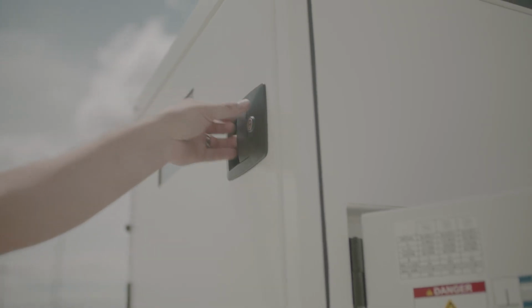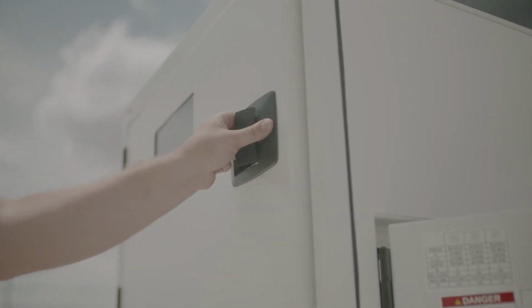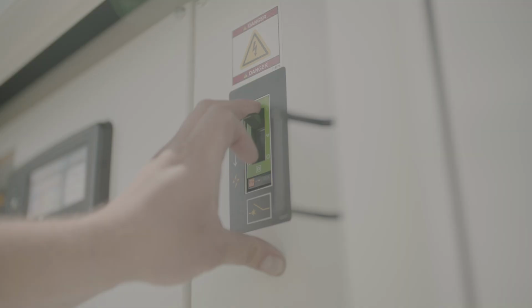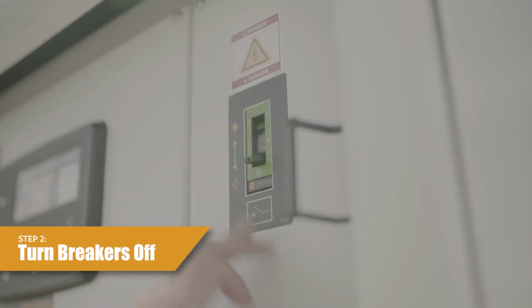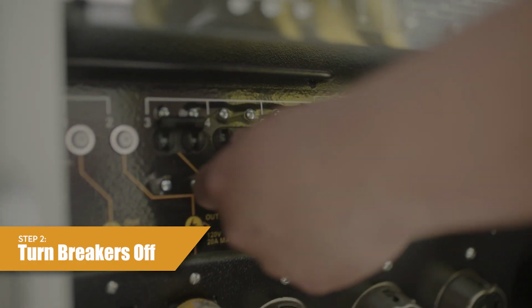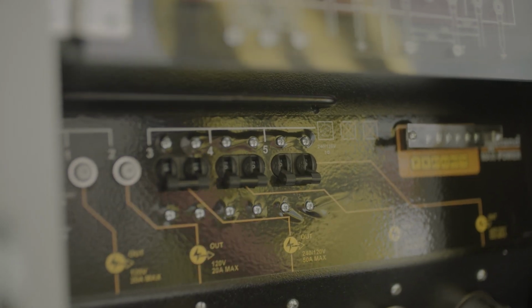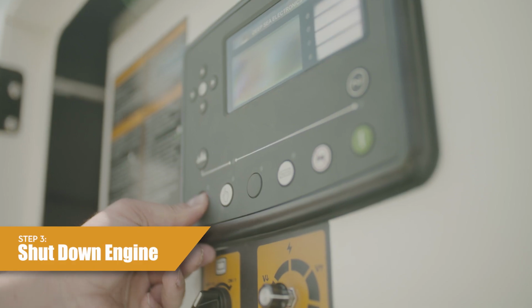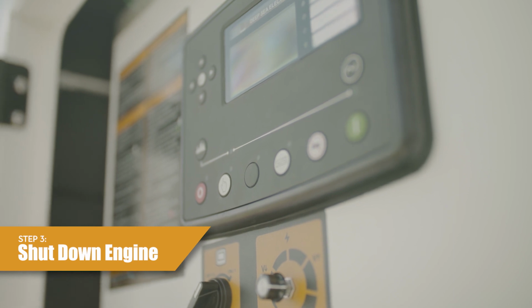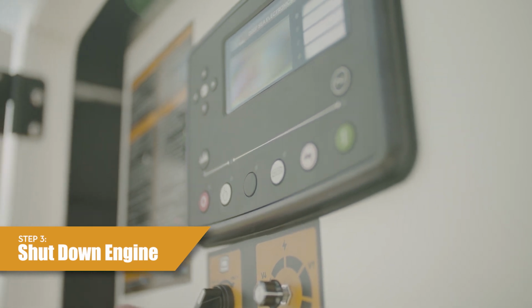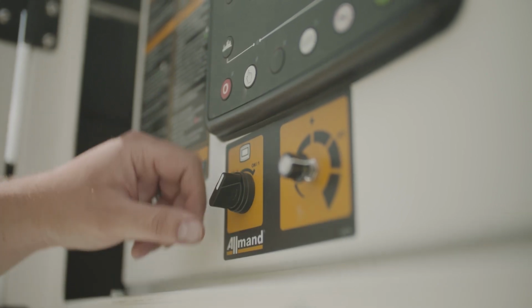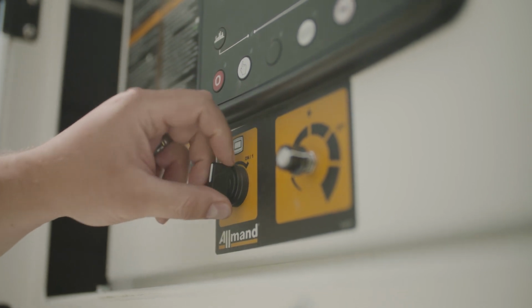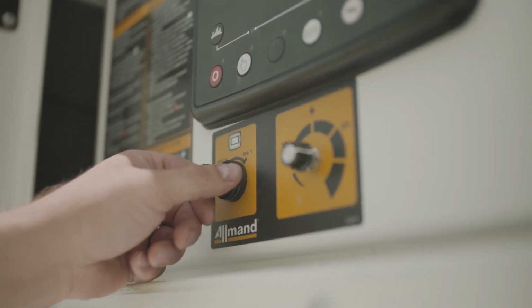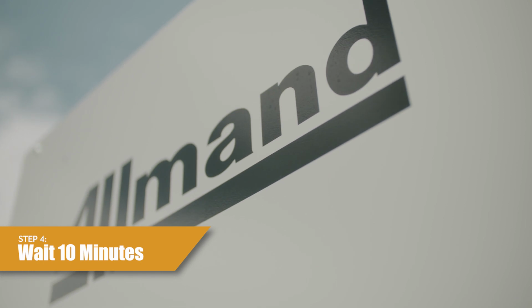To shut down your unit, open the control and AC output panel doors. Step 2. Set all the circuit breakers, main and outlet, to the off position. Step 3. Shut down the engine. Press the stop button to shut down the engine. Set the electronic controller switch to the off position. Step 4. Wait 10 minutes for the unit to cool.